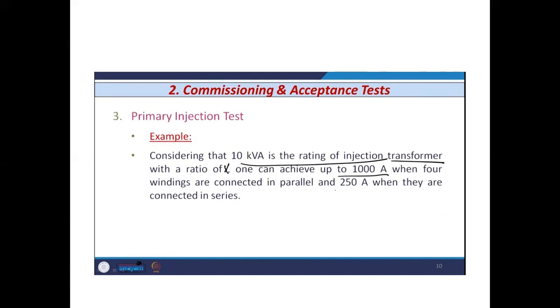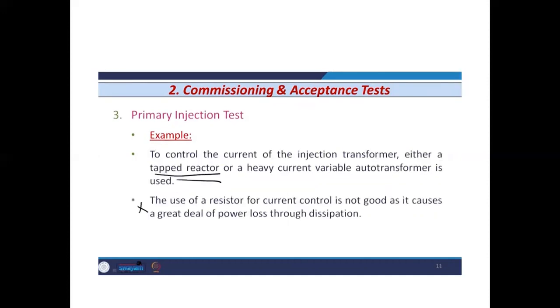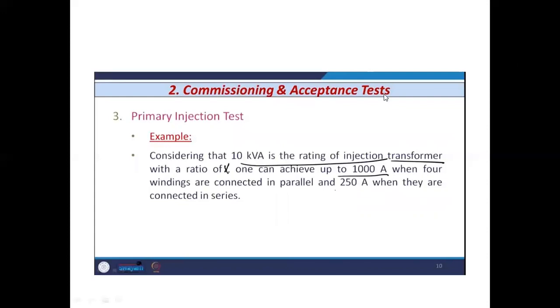This is the example for the primary injection test. Considering that 10 kVA is the rating of the injection transformer with a ratio of 1, it can be tuned up to 1000 ampere when four windings are connected in parallel and 250 ampere when they are connected in series. So if they are connected in series, we will get 250 ampere. In order to increase the amperes, as I told you in the previous slide, we have to connect the windings in parallel.